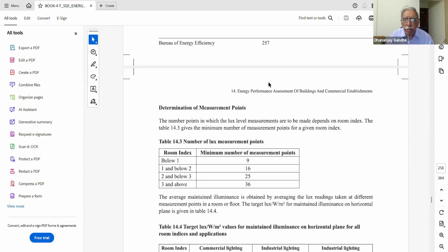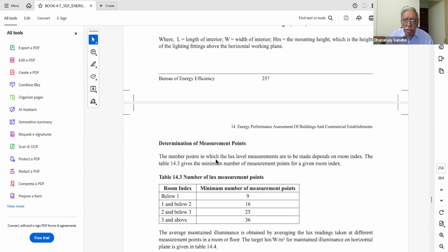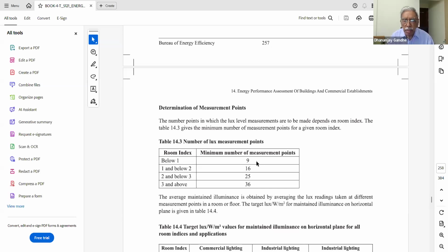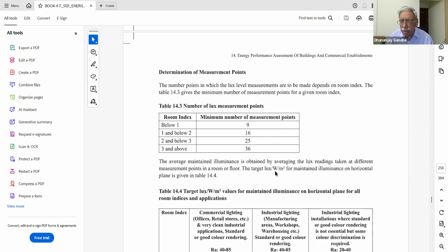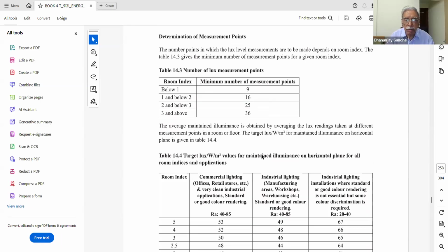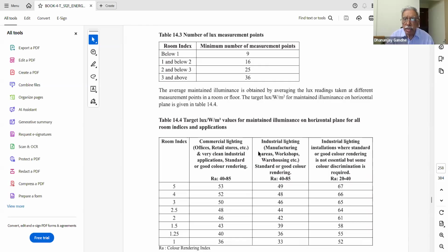If the room index, as worked out by this formula for that particular area, is less than 1, you have to make minimum measurements of illumination intensity at 9 places, and take an average of the 9 readings to get the average illumination intensity in lux. Similarly, if the room index is between 1 and 2, the measurement is to be done at 16 places. If the room index is between 2 and 3, measurements are to be done at 25 places. If the room index is 3 and above, measurements are to be done at 36 places. And then you have to calculate the average of these measurements at so many places in a room.